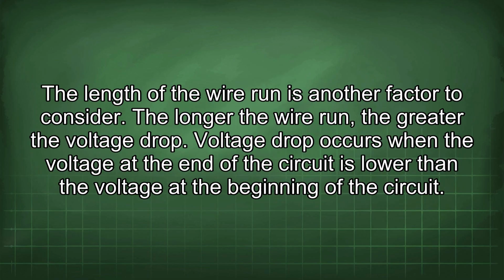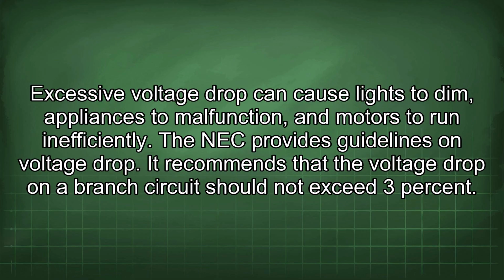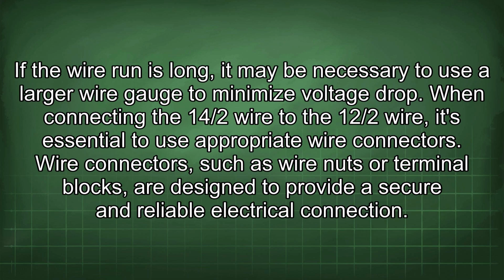The length of the wire run is another factor to consider. The longer the wire run, the greater the voltage drop. Voltage drop occurs when the voltage at the end of the circuit is lower than the voltage at the beginning of the circuit. Excessive voltage drop can cause lights to dim, appliances to malfunction, and motors to run inefficiently. The NEC provides guidelines on voltage drop. It recommends that the voltage drop on a branch circuit should not exceed 3%. If the wire run is long, it may be necessary to use a larger wire gauge to minimize voltage drop.